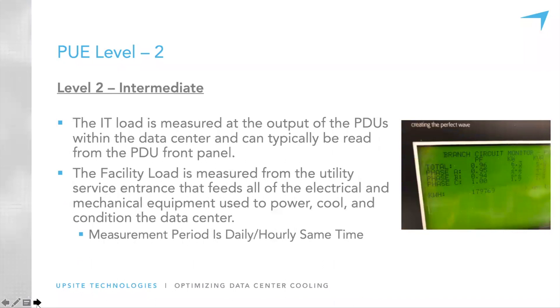PUE Level 2 looks at measurements from the floor PDUs within the data center. We have the ability to see the load across the phases. On a weekly basis, I go to the floor PDUs, check which UPS system they're tied to, and do a check and balance. It might not always be exact due to power factor, but should be very close to what I see from the floor PDU to the UPS system.